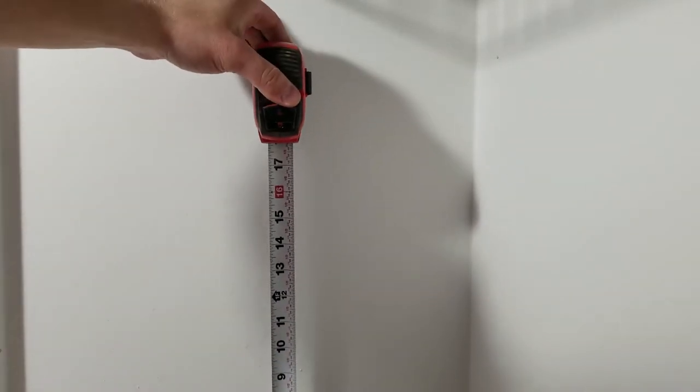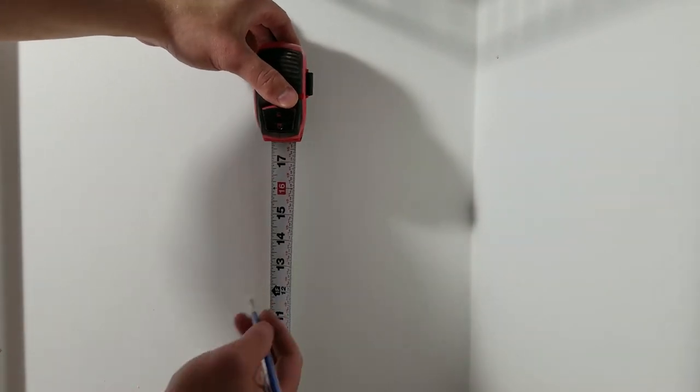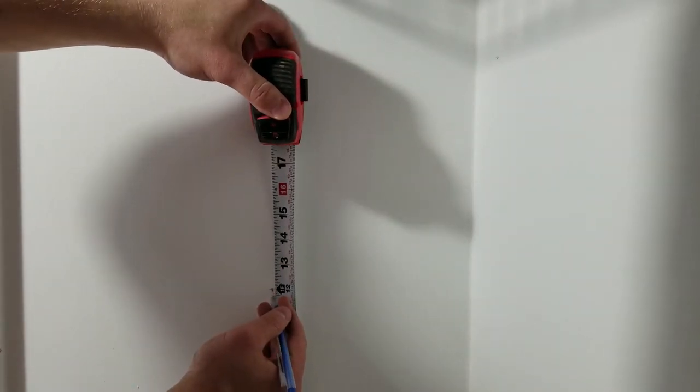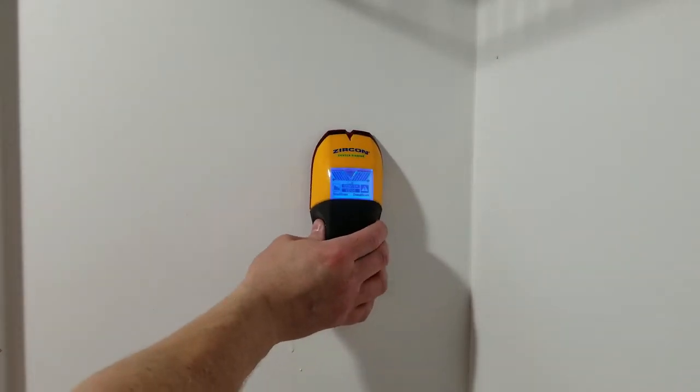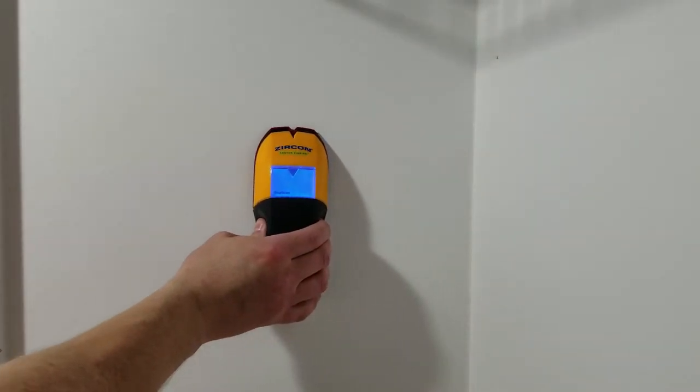Here I'm measuring the height of my outlet box. Typically the bottom of the outlet box will be about 12 inches above the finished floor. I'm going to locate my stud again so I know exactly where to cut the hole for my new outlet box.